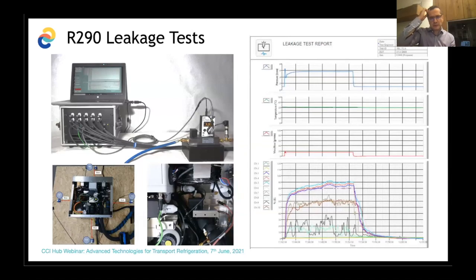This was done also with David Colburn. I think he's known in the community. Also, we jointly developed a system for how to assess that, and at the end of the day, we found out what the potential ignition components and subsystems within the unit are. Basically, we've managed that by providing a highly sealed electronic box, let's put it that way. We've exchanged all the fuses. We don't have any fuse in the system. Everything is happening on a platen where the ignition sources are low, in a gas-sealed box. We are using ATEX certified components where needed.